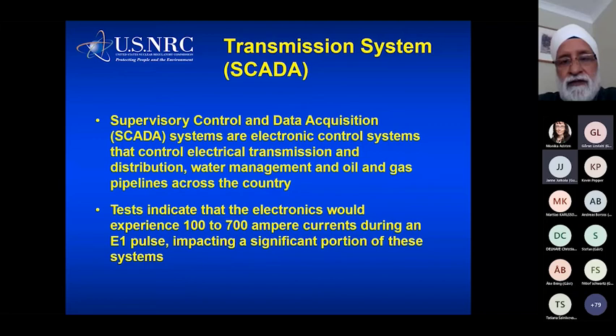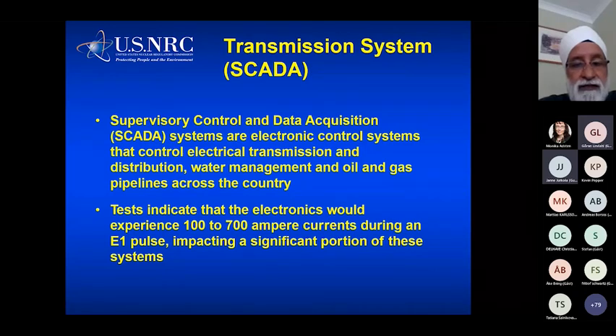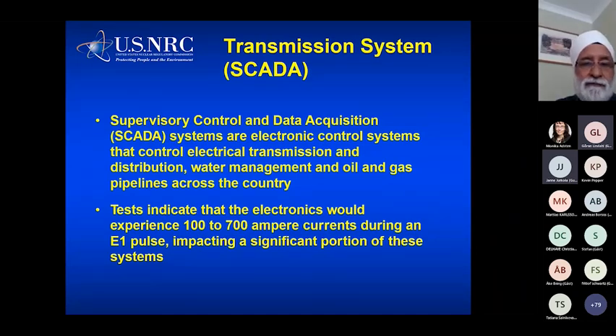In the transmission systems, the SCADA, as we call it, supervisory control and data acquisition systems, they are vulnerable because it's mostly electronic and we use them all over the place. We use them in our nuclear power plants, the transmission systems, water management, oil and gas pipelines throughout the country. And what we found by testing is that electronics can experience up to about 700 amps during the E1 pulse. So it's a significant jolt to the system.